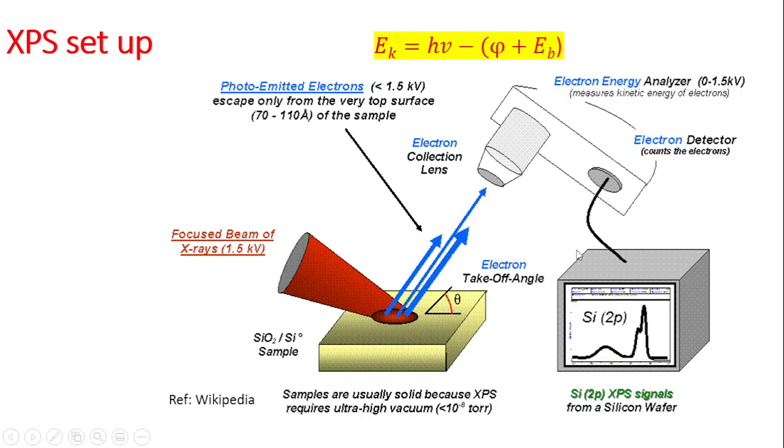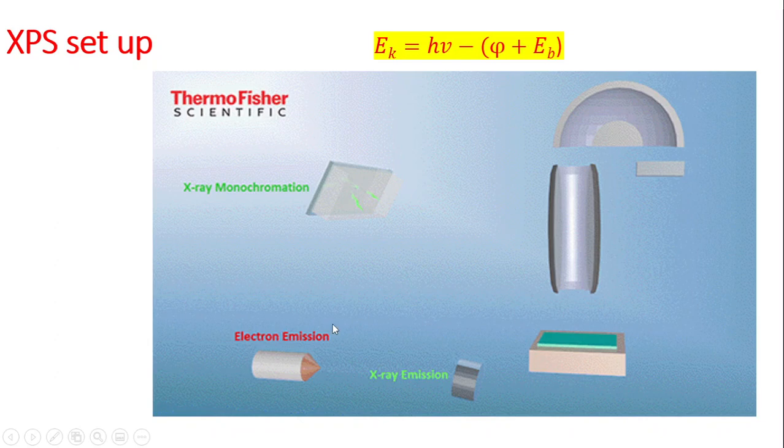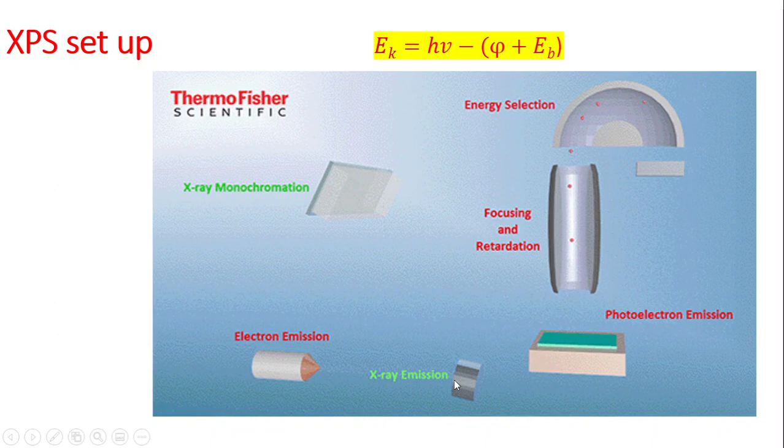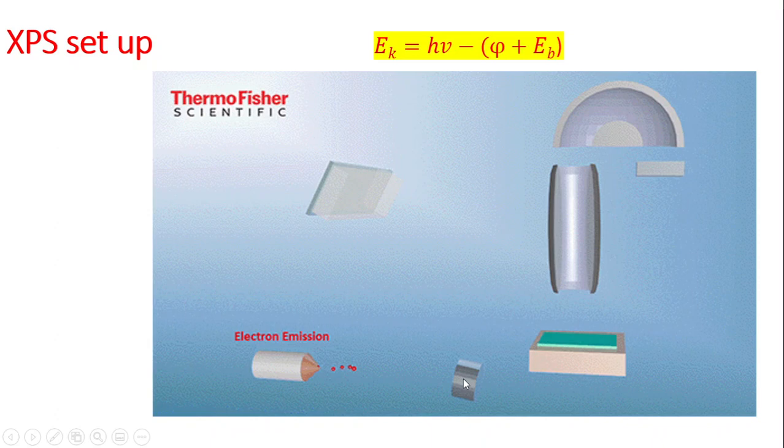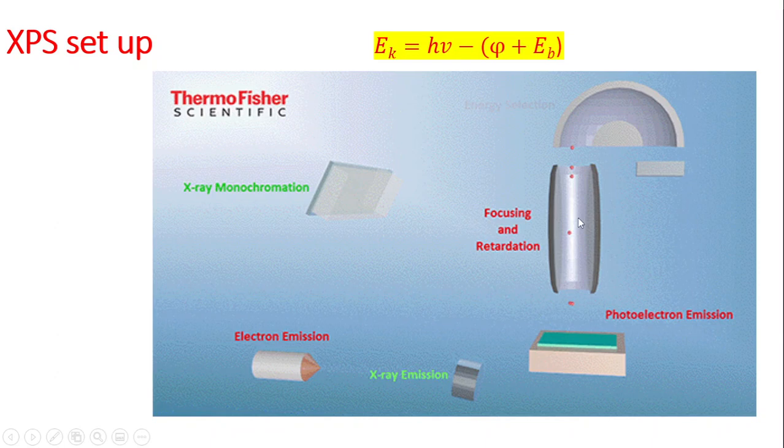This animation shows how the XPS process works. An electron beam source bombards electrons onto an X-ray target like copper or aluminum, which emits X-rays. These X-rays are focused onto a monochromator, which reflects the light onto the sample. The sample emits photoelectrons that are collected by the detector, and this information is converted into intensity and binding energy.